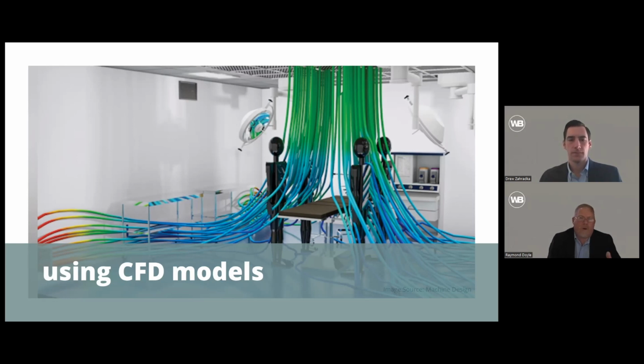And if all you're worried about is that one zone within the room, it's a proof of concept. It verifies that based on where the returns are and where the supplies are, that air is not going to recirculate back on top of itself in the room. So CFD does a great job of proving that design concept. In some cases, it's less important, and it's more important to just make sure you use good standard practices and use particle counters to make sure you're doing things correctly.